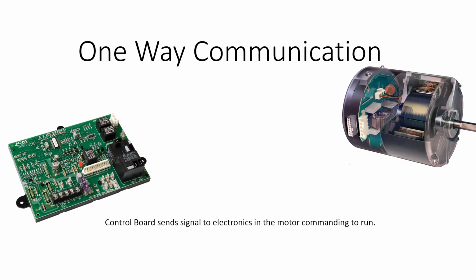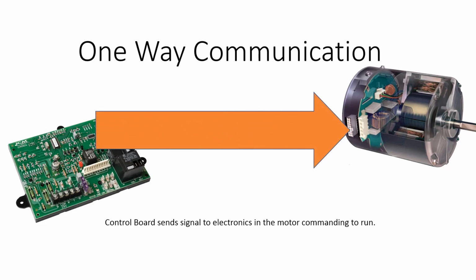There are a couple of different ways that ECM motors communicate. The first one is one-way communication, where the control board tells the motor whether it's in heating or cooling mode, and the electronics in the end of the motor decide where it needs to run for each mode of operation.